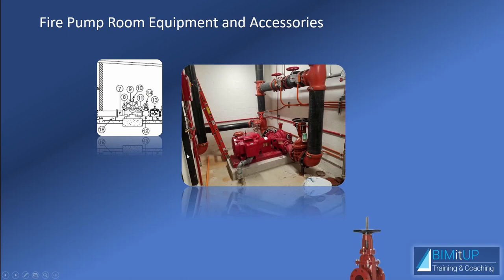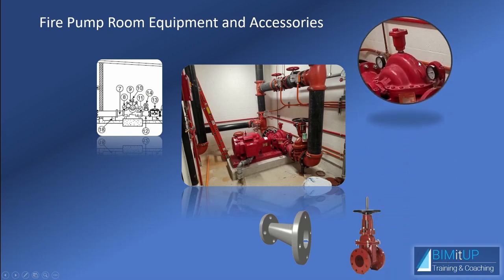So let's take a look at those. This would be that OS and Y right here. That's that eccentric reducer. This would be the casing with the suction and discharge pressure gauges and that air release at the top. Something to keep in mind is that many people confuse cavitation with those air bubbles. Those are different, and we go in depth on.